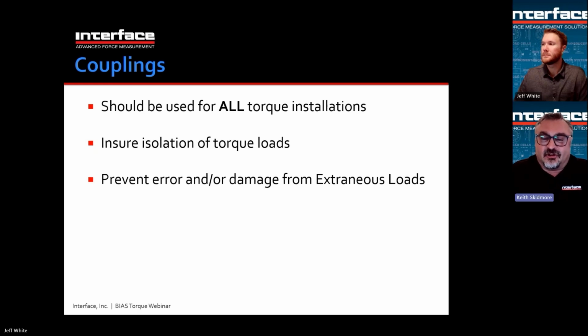What a coupling does is ensure isolation of the torque loads. A coupling will transfer torque loading to the sensor, but will not transfer extraneous loads. So just like a load cell, torque sensors are sensitive to off-axis loading. Those loads create errors. They also can damage the sensor. So a coupling prevents that. Without a coupling, a misalignment in the driveline can create large bending loads and side loads into the sensing elements that are, at the very least, error producing, but it also can ruin the sensor, which is not desirable at all.